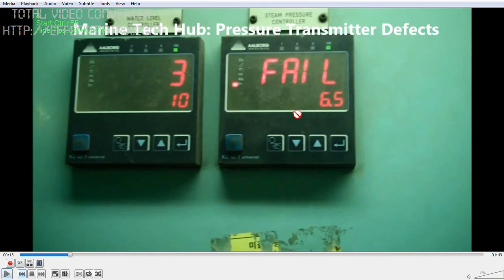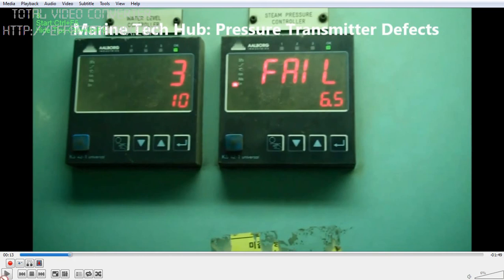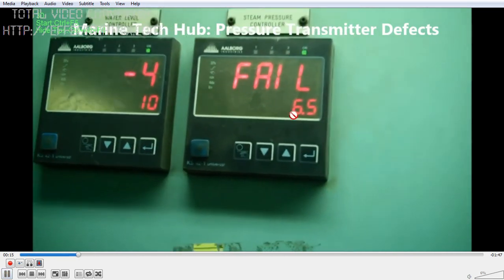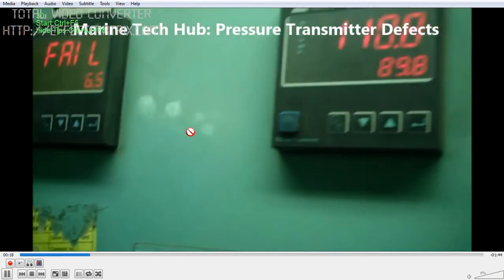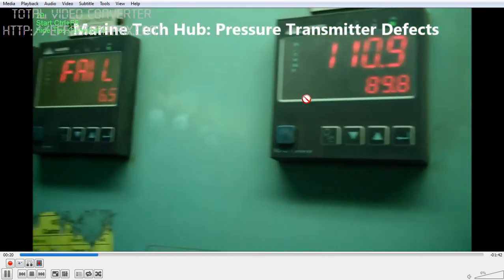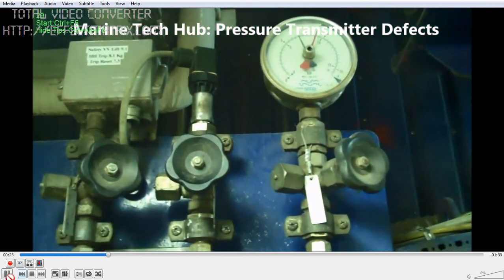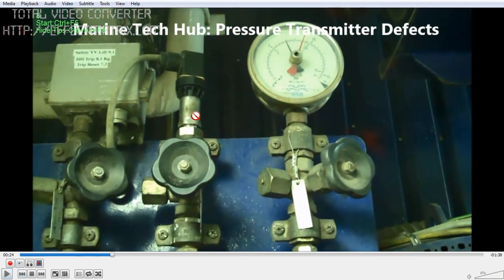Next, we will be opening this steam pressure controller and checking what the fault is. We checked through the parameters that were given — this FAIL condition is not listed. So I will explain how you find the defects. You need to open this controller and take it to the workshop. This here is the pressure transmitter, and from it we get 4 to 20 milliamps. From here the signal goes to the controller.